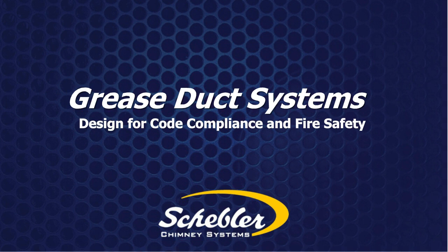Okay, what about field conditions that are different from what is shown on the floor plan with the system? Since it's factory manufactured, are variations of a few inches accounted for? In grease duct systems, we have what we call variable sections built into our design. So it would not be uncommon to have a few inches of variation one direction or the other. So our engineers, when they design a grease duct system, as they would in a boiler flue system, account for that by having variable sections throughout the system that allow for several inches of adjustability as the product is being assembled in the field.